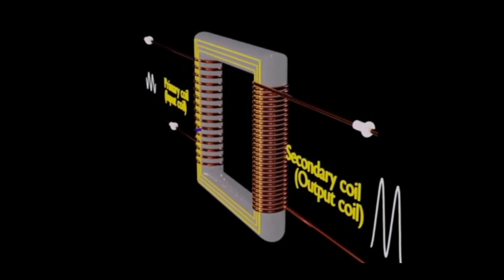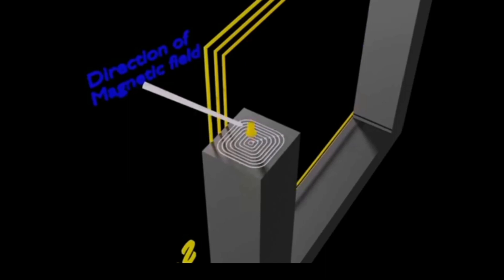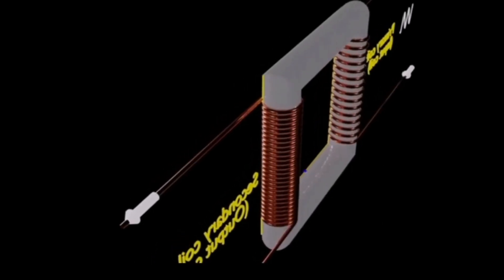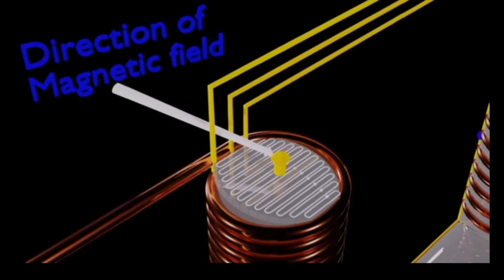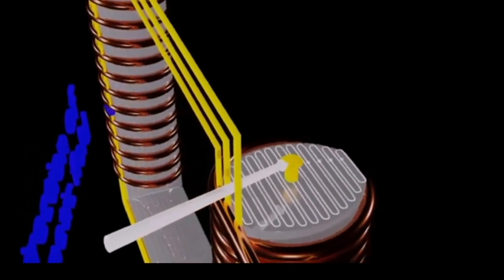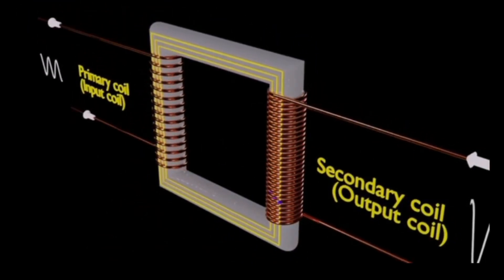Let's visualize this by first considering a solid iron core instead of thin insulated metal sheet layers. In the cross-section of the solid iron core, since the current in an eddy current loop is proportional to the area of the loop, in the case of a single solid iron core the eddy current formation will be very high, and thus there is a higher power loss in the form of heat loss. On the other hand, if we use thin insulated metal sheets stacked in layers, the layers of insulation serve as a barrier to eddy currents, so eddy currents can only flow in narrow loops within the thickness of each single lamination. Since the current in an eddy current loop is proportional to the area of the loop, this prevents most of the current from flowing, reducing eddy currents to a very small level. Thus there is lesser power loss in the form of heat loss.